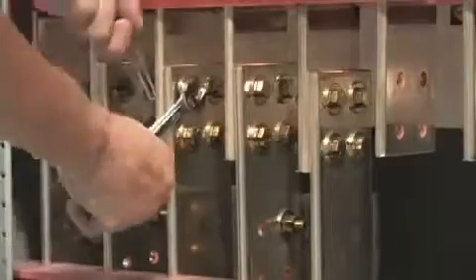The bus was designed with field interchangeable links that allow the user to change the configuration in the field simply by unfastening the four bolts connecting the bus link to the main bus and reattaching the bus link to the opposite side of the main bus.